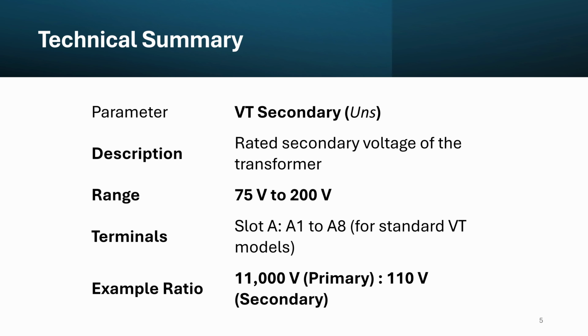Think of VT secondary like a foreign language interpreter. The high voltage system speaks 11,000 volts, but your relay only understands 110 volts. The VT secondary setting is the relay's interpreter. It tells the relay exactly how to translate those small words back into big words.